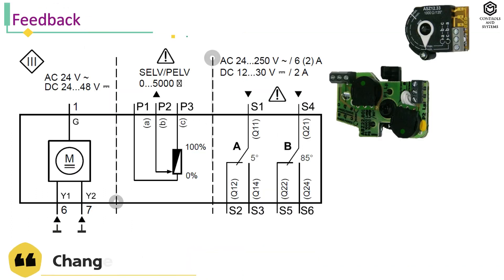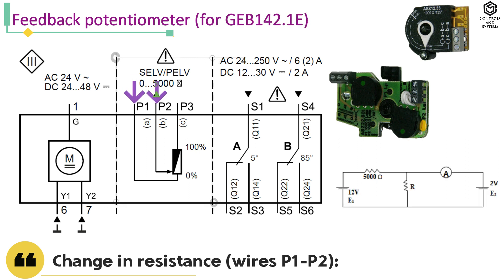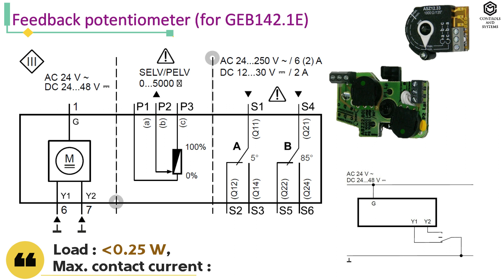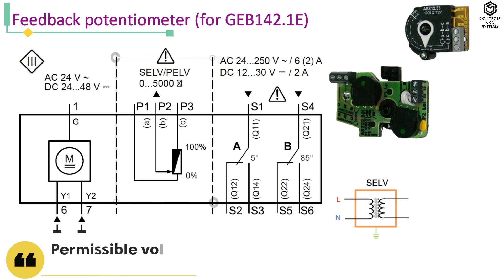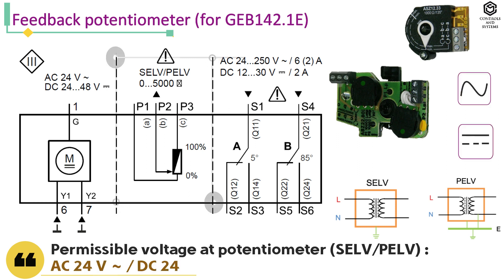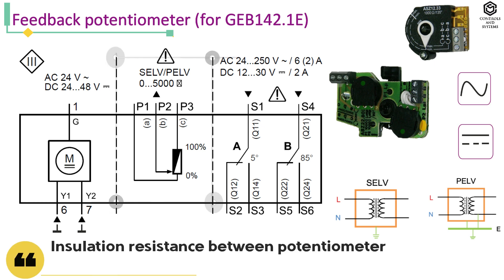Outputs — feedback potentiometer: change in resistance between wire terminals P1 and P2 is 0 to 5000 ohm, load is less than 0.25 watt, maximum contact current is less than 0.1 milliamps. Permissible voltage at potentiometer is AC 24 volt or DC 24 to 48 volt. Insulation resistance between potentiometer and housing is AC 500 volt.